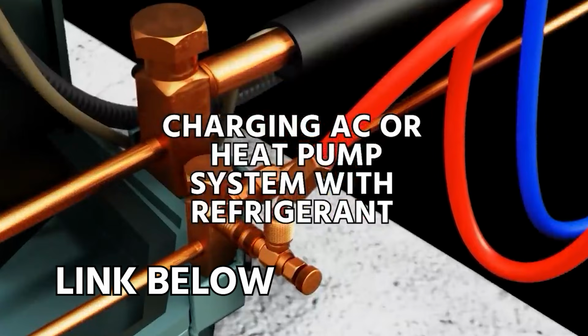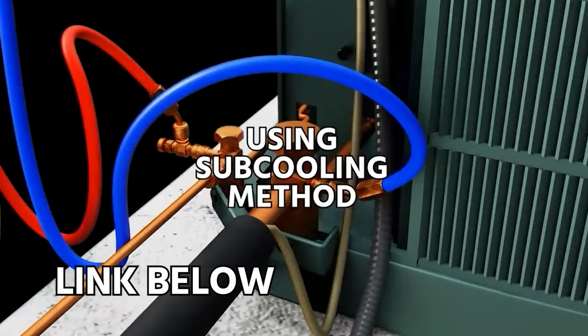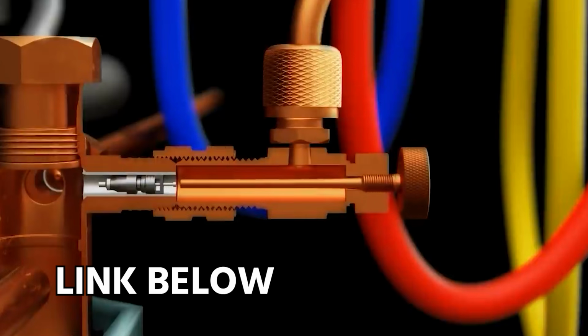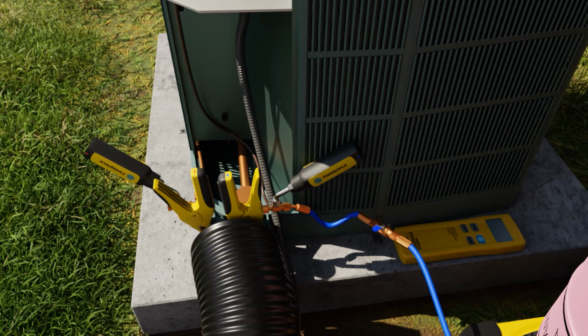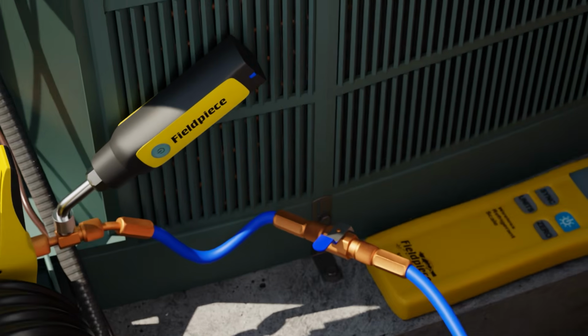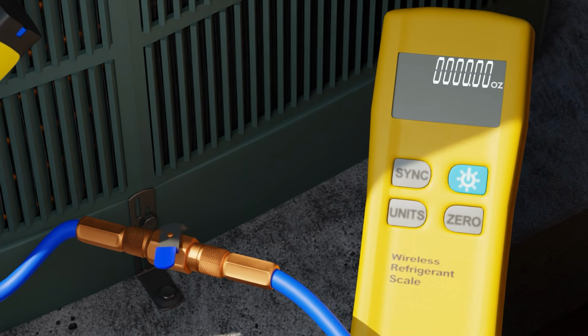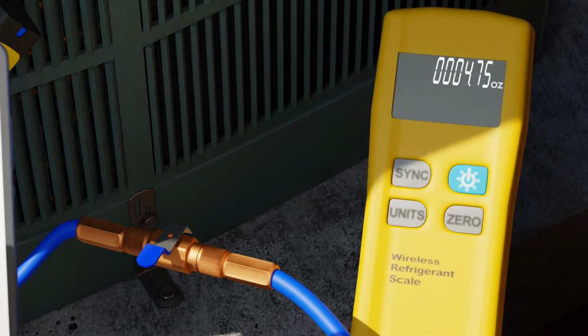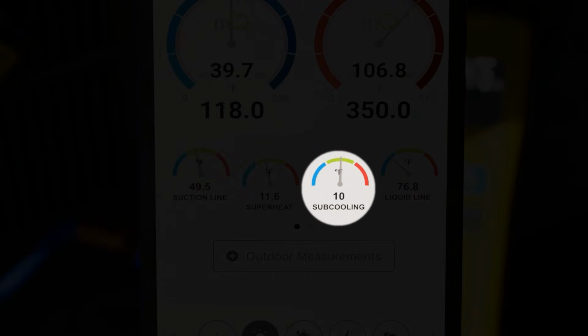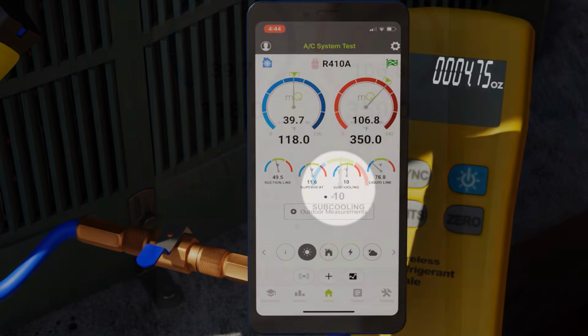If you want to know more about how to add charge to a system, we have a completely separate charging by subcooling video that you can watch. Again, we only do this once we've taken all of our measurements and the system has run a sufficient amount of time, but we're going to show adding some refrigerant until we get to the target 10 degrees of subcooling. Here I show only having put in 4.75 ounces, and you can see we achieved 10 degrees of subcooling. Now again, only do this after an appropriate amount of runtime.